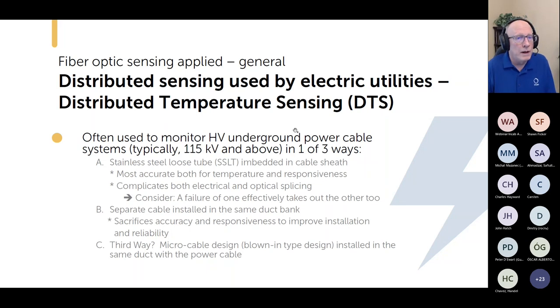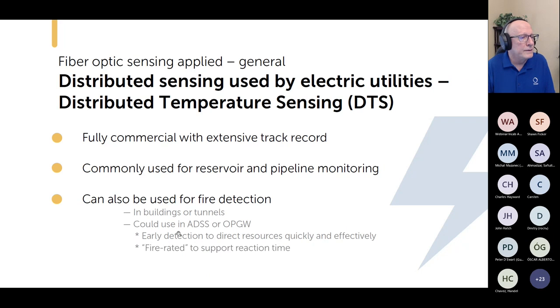DTS is already used a lot by utilities, but not the way I just talked about in ADSS or OPGW. Instead, it's often used in high voltage underground power cable systems. Ten to fifteen years ago, because of the cost of the technology, it was pretty much limited to 115 kV and above. And there were three ways that it could be done. But today, the cost of doing it has gone down a lot.